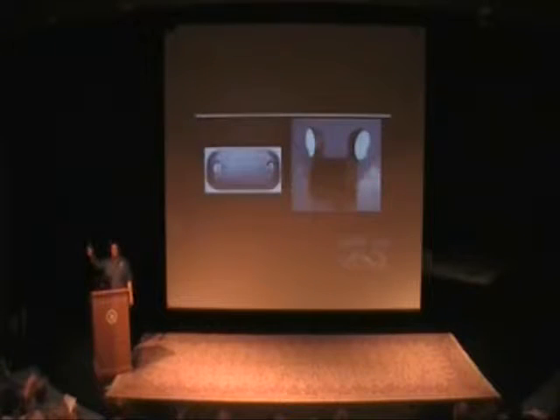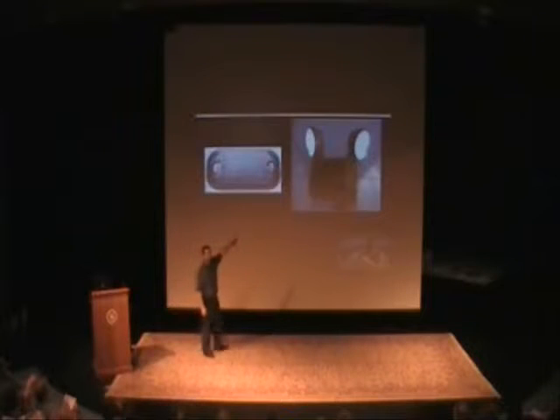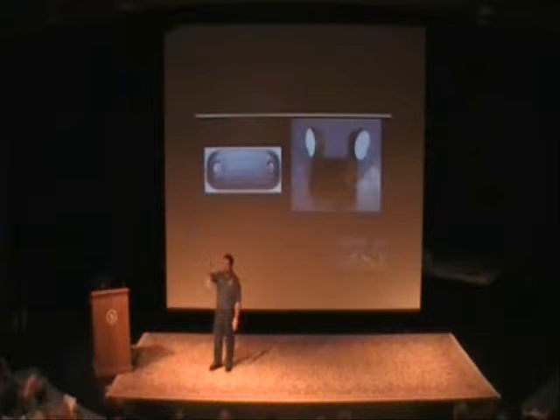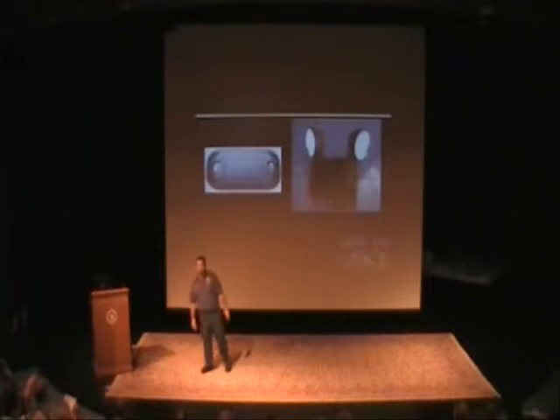Once again, you as the crowd manager don't have to do all of the physical work, but you have a guy pushing his broom. You can say, hey, take that broom handle up there and push on that button and hold it. And count. 1, 1,000, 2, 1,000, 3. Have them count to 30 seconds. What that does, that takes the battery and depletes it a little bit. Then it gives it a chance to recharge. That's exercising your battery. If you don't exercise it, within 5 years you're replacing it.